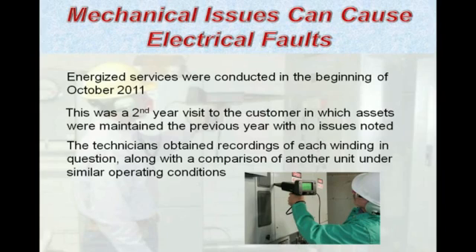In this particular case, we have two units that are identical as far as manufacturer, as far as rating, loads being served, and load level. So with ultrasound, it is always important whenever possible, and particularly in electrical applications, to utilize comparisons. They can be very telltale and give us a good starting point.